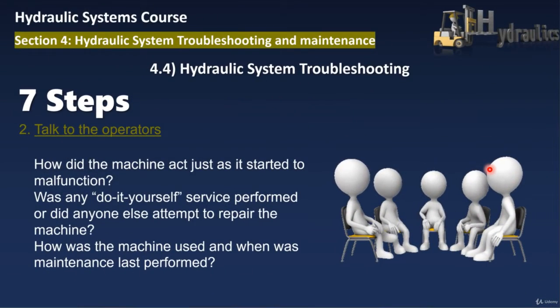Then you need to have a small meeting with the operator, or the person who is continuously monitoring the hydraulic machine or hydraulic system, and ask some questions. How did the machine act as it started to malfunction? What was the issue, what was not normal that you observed when the machine started to malfunction? Did anyone perform do-it-yourself service, or was this machine subjected to previous maintenance? Did anyone else attempt to repair the machine?